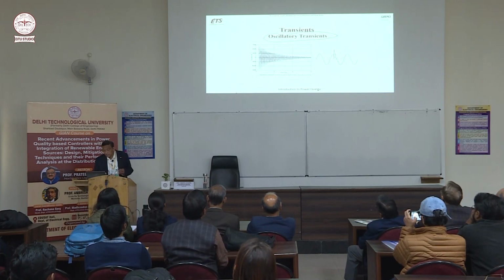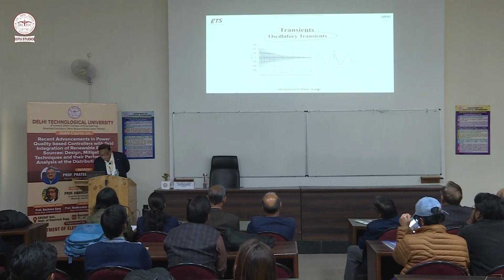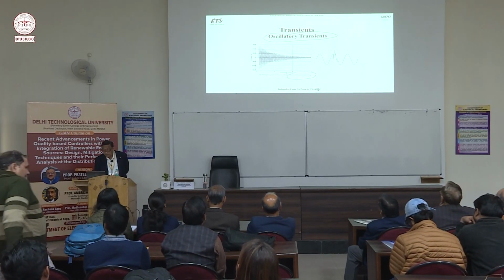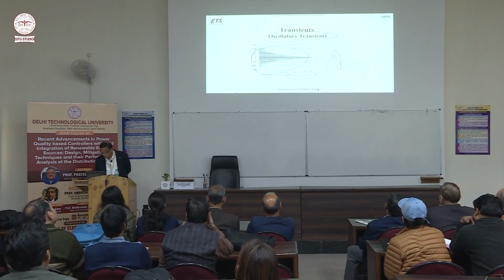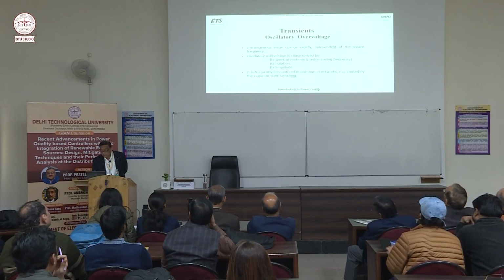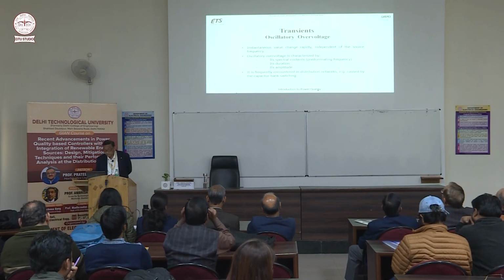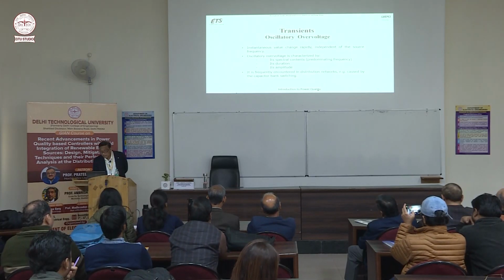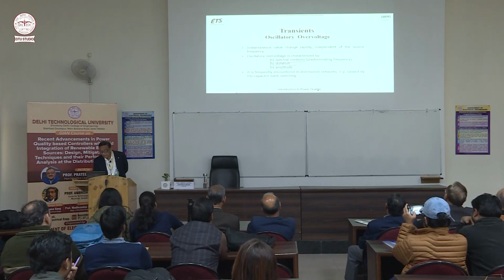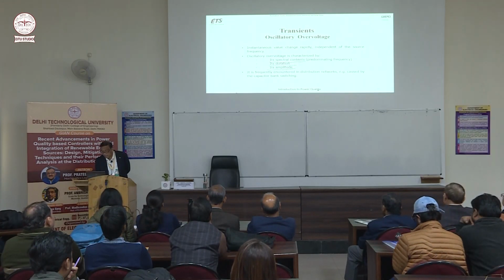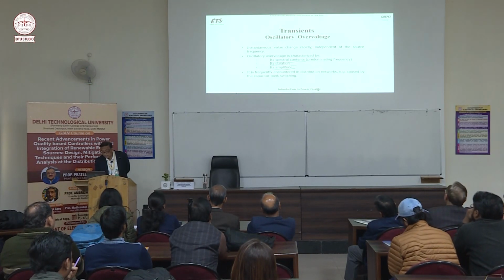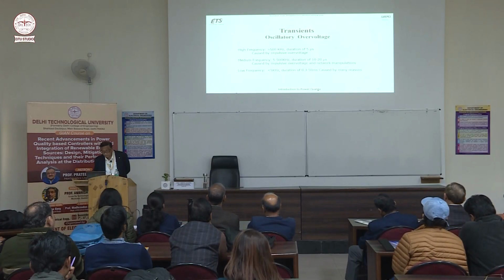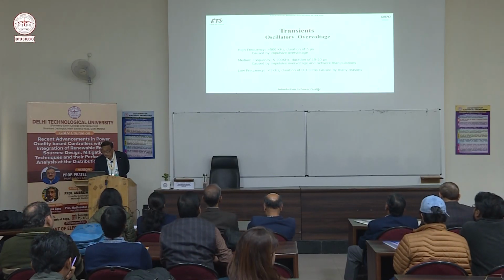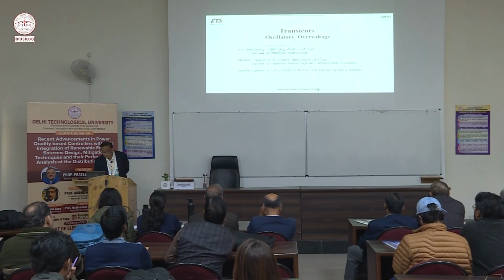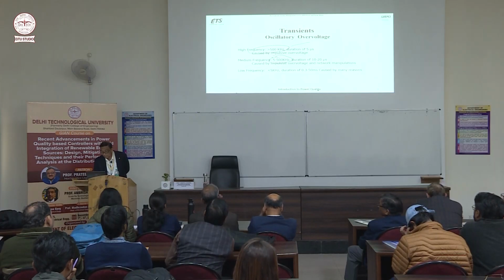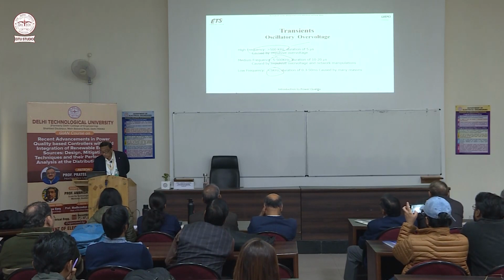Oscillatory transients, this is just an example of transient caused by capacitor switching, back-to-back capacitor switching. So you can see oscillatory transients are there, high frequency oscillatory transients. Instantaneous value change rapidly independent of the source frequency. So oscillatory over voltage is characterized by spectral content, its duration, its amplitude. It is frequently encountered in distribution network, caused mainly by the capacitor banking. Depending on the capacitor and inductance, it may be high frequency, 5 to 500 kilohertz or less than 5 kilohertz.